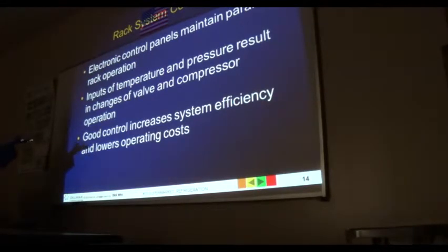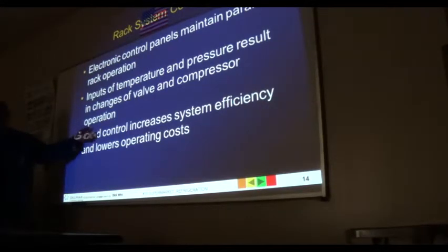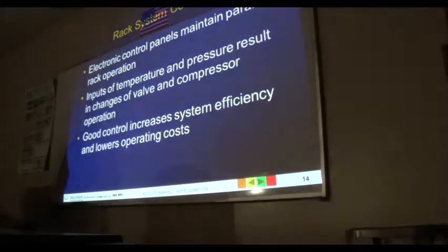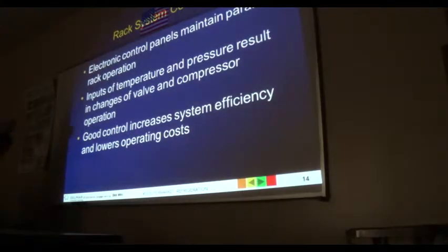Right, so if I had a 6-cylinder compressor, it'll be running on 2 cylinders. It would be running at 33% to give me 1/3 of the efficiency or the capacity. If I want full capacity, then I can release the valve and let the valve start operating, and it gives me the full capacity.